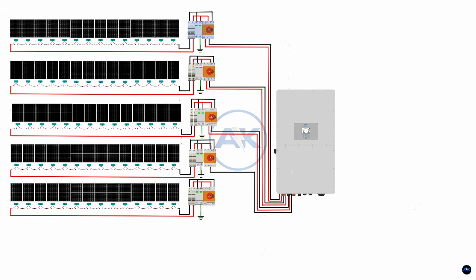Connect the SPD positive terminal to the positive bus bar, the negative terminal to the negative bus bar, and the earth terminal to the grounding bar. Make sure the grounding cable is short and securely connected.